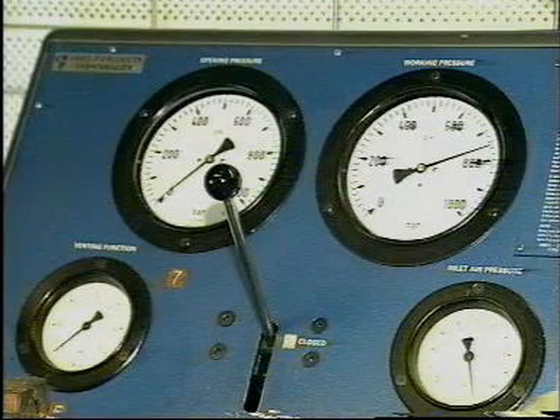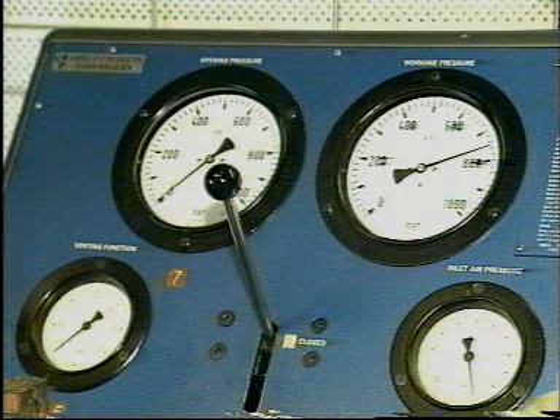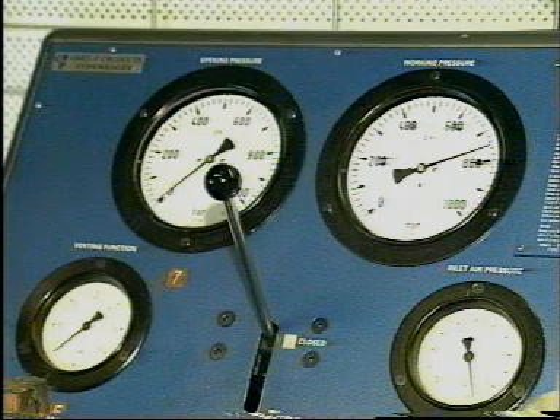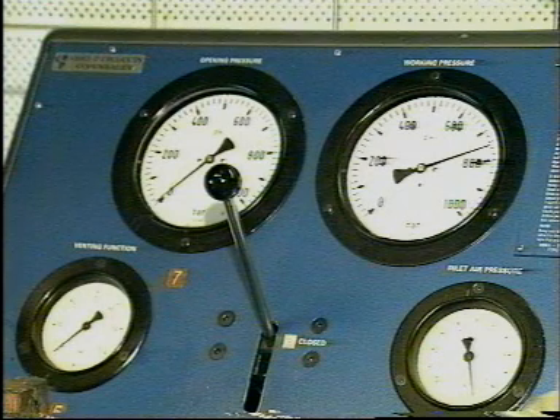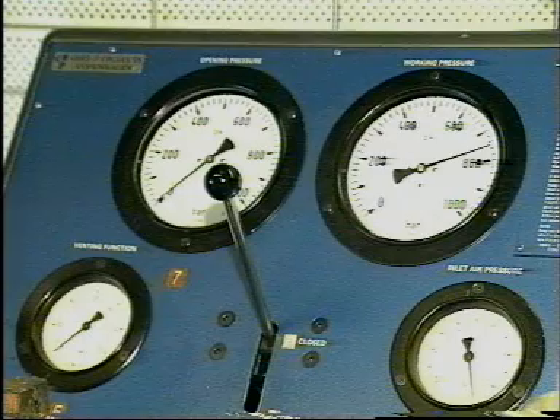The main objective of the normal tests shown in Part 3 of this film is to ensure that the valves function at the correct opening pressures and that they seal tightly. As the injection capacity of the engine fuel pump is much greater than that of the pressure testing pump, atomization will be ensured during service, provided that the fuel valve passes the normal tests.